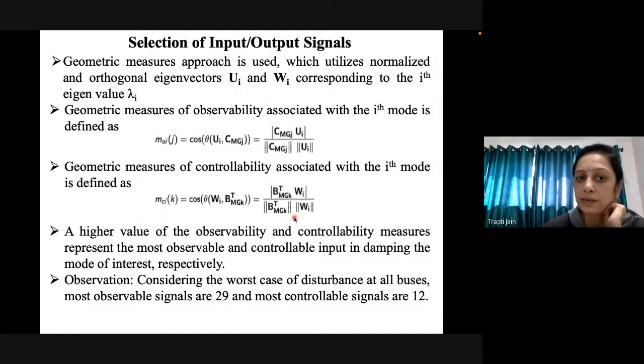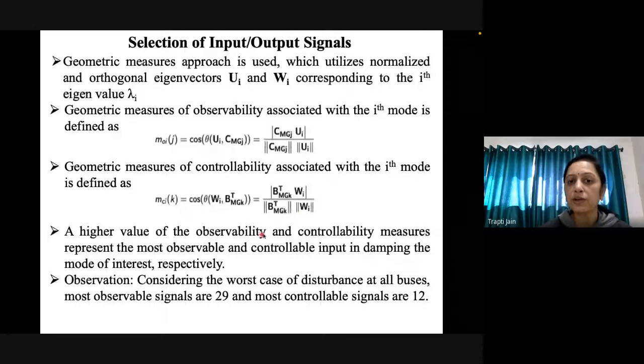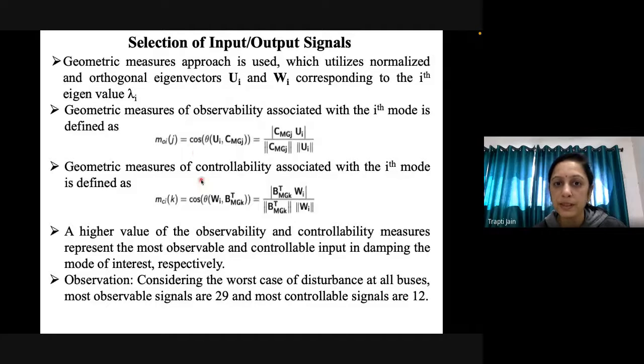We calculated these values, and a higher value of the observability and controllability measures represents the most observable and controllable input in damping the mode of interest, respectively. We calculated these values for all the eigenvalues, and from there selected the inputs with high observability and the outputs with high controllability. Considering the worst case of disturbance at all buses, the most observable signals were found to be 29, and the most controllable signals were 12.